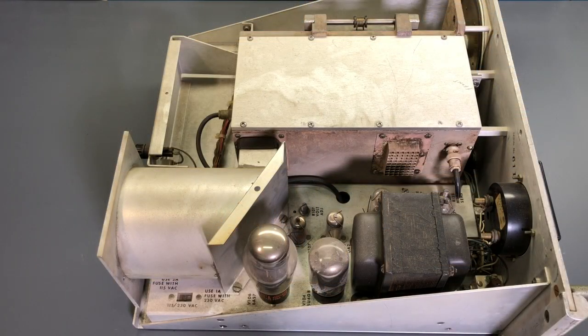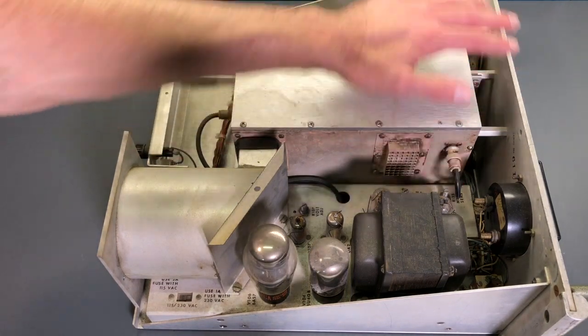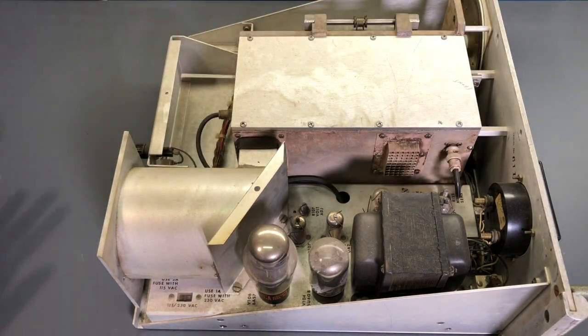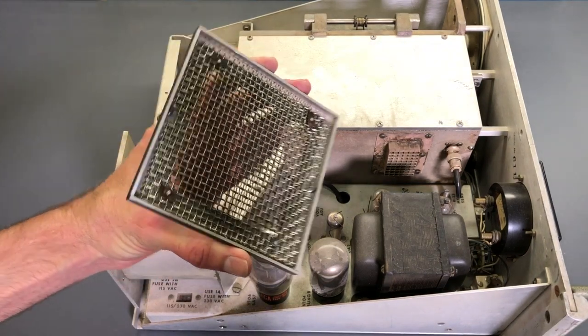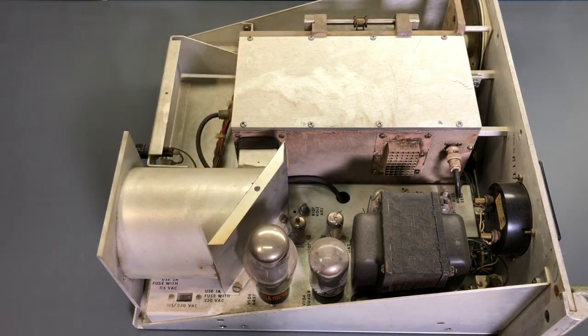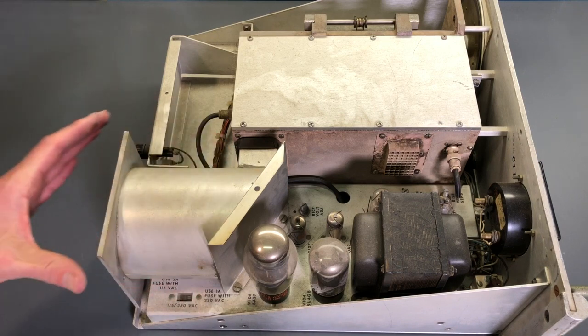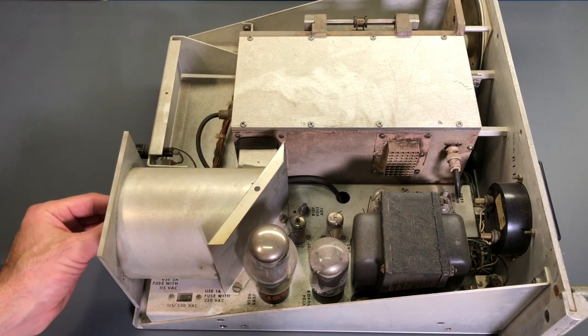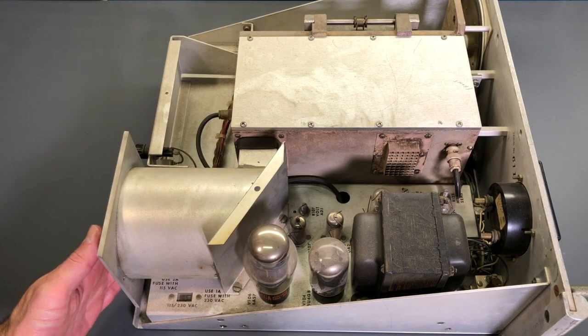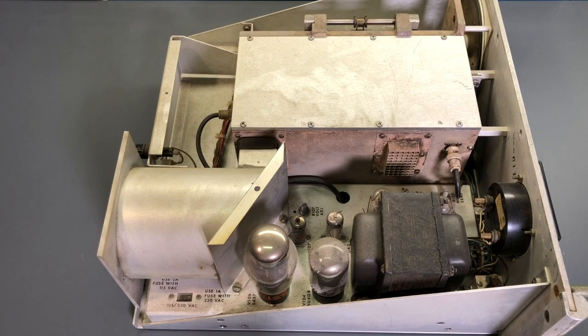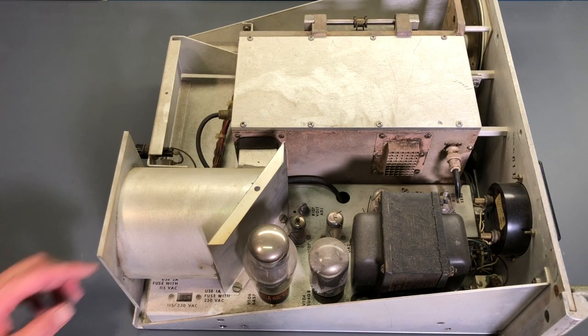Okay, I have the top cover removed. It was just a matter of several screws around the perimeter, and then the cover slipped right off. I also removed this mesh screen that was on the fan on the back. The fan is inside this tube right here. The motor and everything is inside of here, and I wanted to make sure that the fan rotates smoothly, and it does. I want to be able to watch that when it's powered up as well, and make sure that it's running correctly. There's some dust, not really lint, but sort of a film in there that's built up that needs to be cleaned out as well.